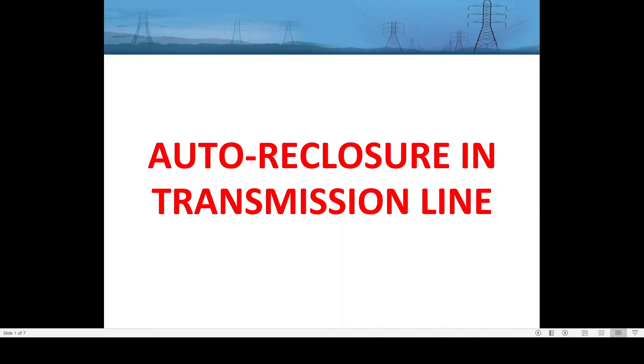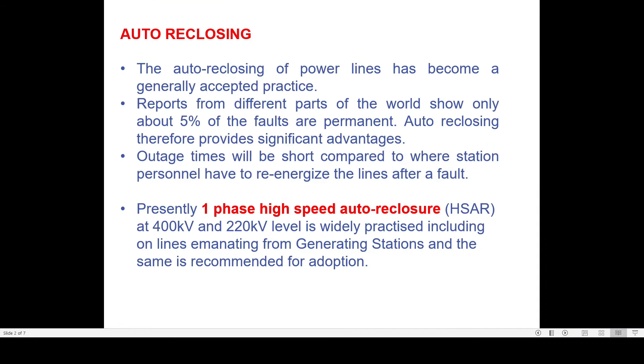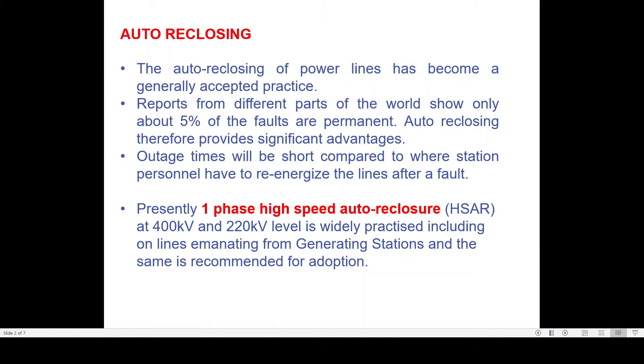Without wasting further time, let us start with today's session on autoreclosure. Autoreclosing of power lines is a very generally accepted practice across different utilities. Autoreclosures are generally implemented for overhead transmission lines because reports from different parts of the world have shown that only about 5% of faults are permanent in nature.